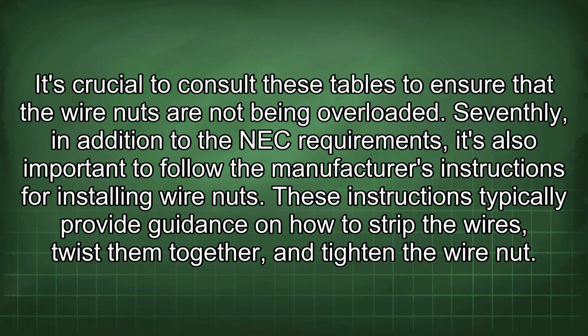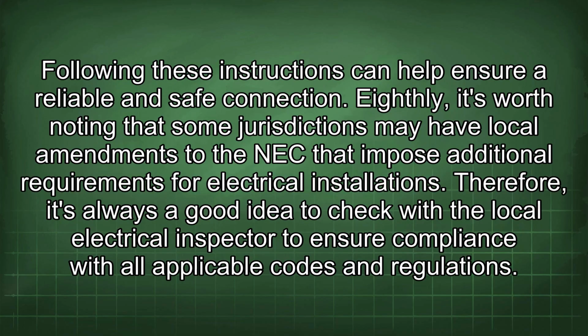Seventhly, in addition to the NEC requirements, it's also important to follow the manufacturer's instructions for installing wire nuts. These instructions typically provide guidance on how to strip the wires, twist them together, and tighten the wire nut. Following these instructions can help ensure a reliable and safe connection. Eighthly, it's worth noting that some jurisdictions may have local amendments to the NEC that impose additional requirements for electrical installations. Therefore, it's always a good idea to check with the local electrical inspector to ensure compliance with all applicable codes and regulations.